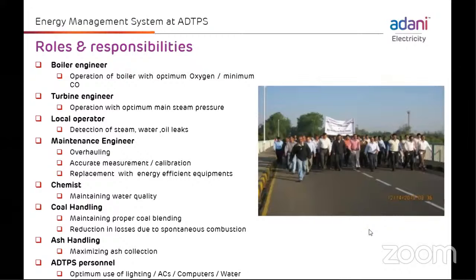For achieving this, we have defined the roles and responsibilities of the various operating staff. For example, the boiler engineer should operate the boiler with optimum oxygen and minimum CO. These are a few examples which directly affect energy usage. The turbine engineer should operate with optimum main steam pressure. The local operator detects steam, water and oil leaks. The maintenance engineer handles overhauling, accurate measurement, calibration and replacement with energy efficient equipment. The chemist should maintain the water quality, otherwise there is a huge loss because of continuous blowdown in the boilers.